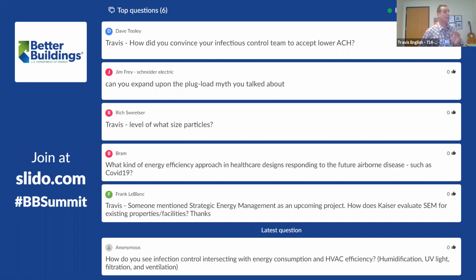So I haven't really had an issue with infection control. For the medical office buildings, it was quite simply that we have a 30-year history of building buildings, and most of those buildings never followed any air change rates. We built commercial buildings, leasing them from landlords, with return plenums and VAV systems all over the place, and there's no difference in quality. Ask a doctor, a patient, or an infection control specialist which of your buildings have 6 air changes and which are sitting at 0.15 CFM per square foot minimum—there's no difference. So on the medical office building side, we made that a national standard around 2011, 2012, and never got a minute of resistance on that.